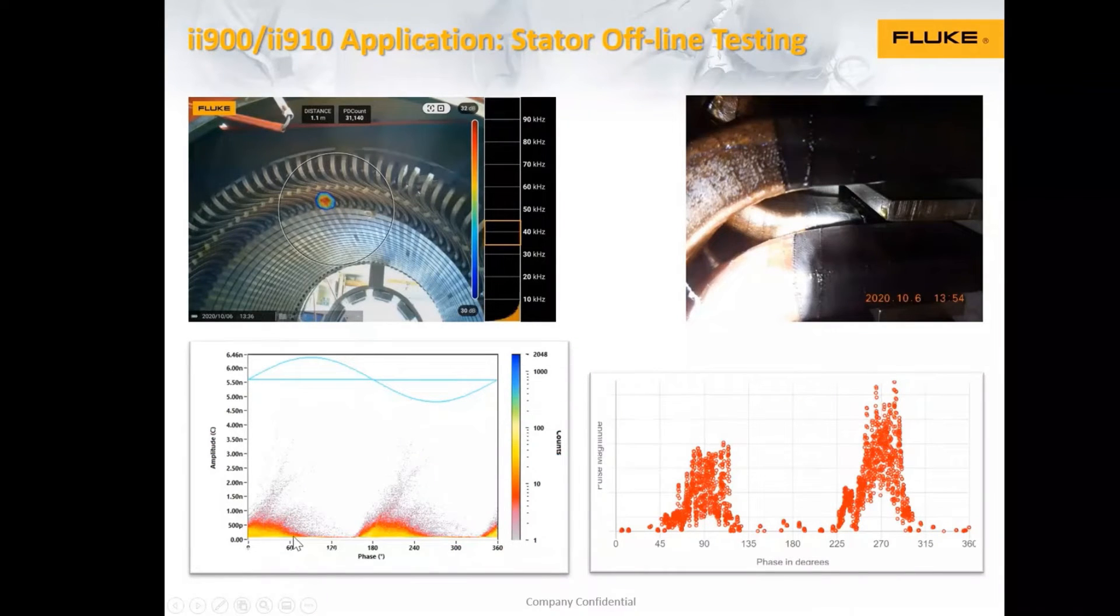We measure here everything, it's a mixture about everything that is happening in the slots, outside of the slots, and so on. With the acoustic camera, we just see that point here, and we see, for example, an asymmetry, and that asymmetry tells me some story. What is going on? Why is it going on? And making a visual inspection, we could identify that spot here, exactly that point that we see here in the camera, we found this point here, and I'm pretty sure you will not see anything, because also I did not see anything really nice. And that machine here had about 800 of positions that can show such a damage, about 800.